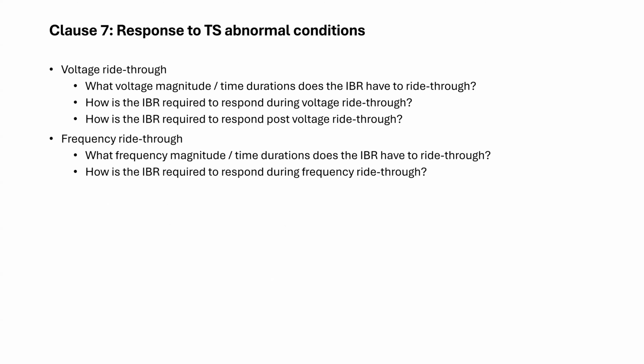Okay, so in this section, we're really covering both voltage and frequency ride-through. And really the idea here of the standard is to describe what are the voltage magnitudes and time durations that the IBR will have to ride through. And then once we're in a ride-through mode, what does the IBR need to do? And then finally, once we return to continuous operating mode or normal operations, how does the IBR transition from a ride-through mode back to normal operations?